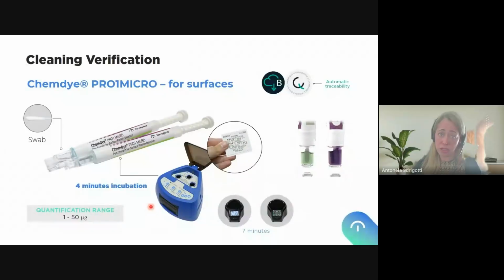This product, since we are saying it is a quantitative device, product or test, we need an incubator calibrated to make the quantification. This is the reason why you see on the screen the Mini Pro, which is a device specifically developed and dedicated for protein tests with 4 minutes incubation. In the same way as all our devices, you will also have a printed ticket because it has a thermal printer built in on the device, and it can also be connected with our software for digitalization and traceability of the results. And most importantly, trend analysis of protein tests and washer performance.